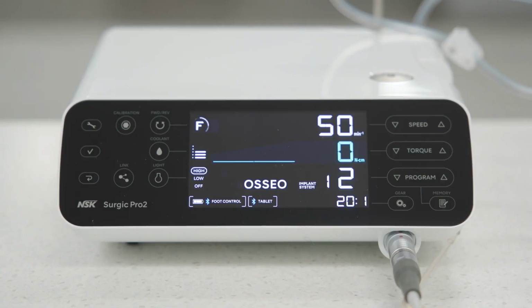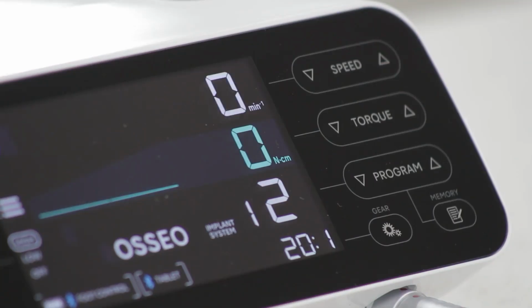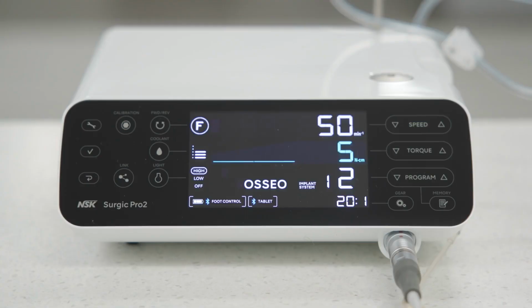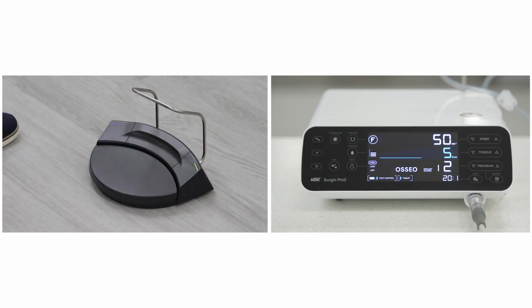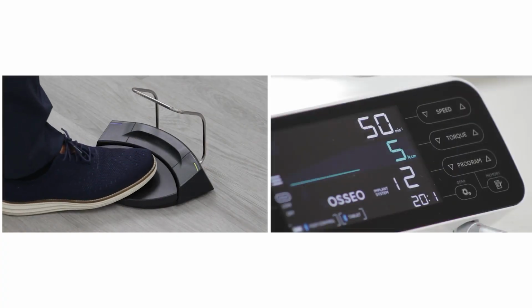If at any point in a procedure a drill becomes stuck in the bone and the load reaches the preset torque upper limit, the error message "Safe" will appear on the display. You will hear a beep and the device will stop. If this happens, release the speed pedal immediately. To clear the error, tap on the speed pedal once.